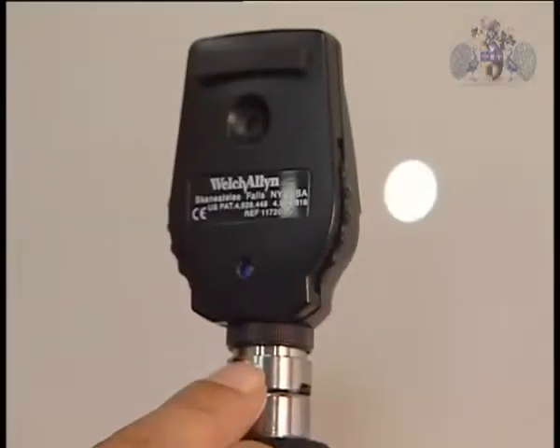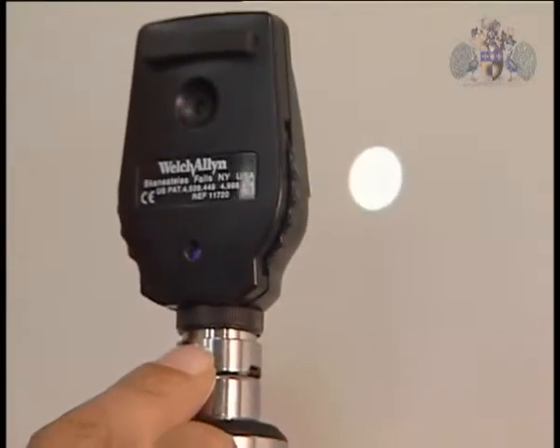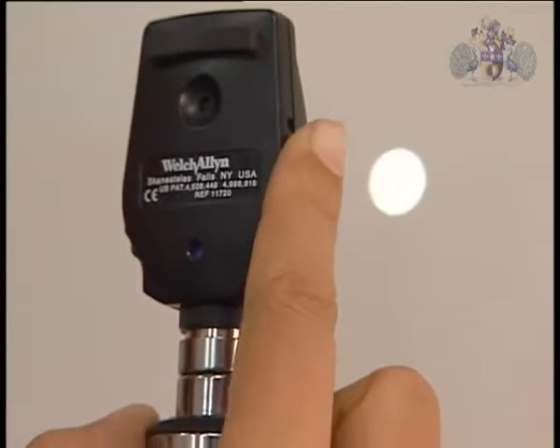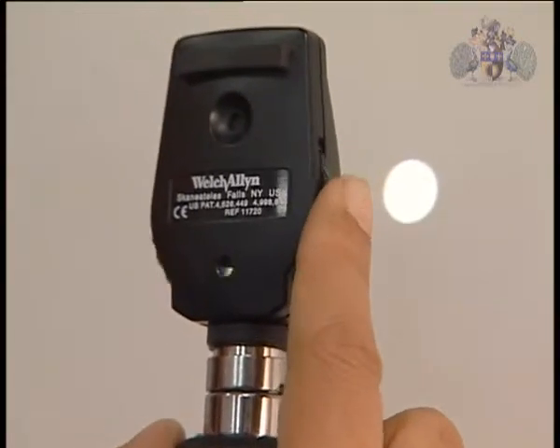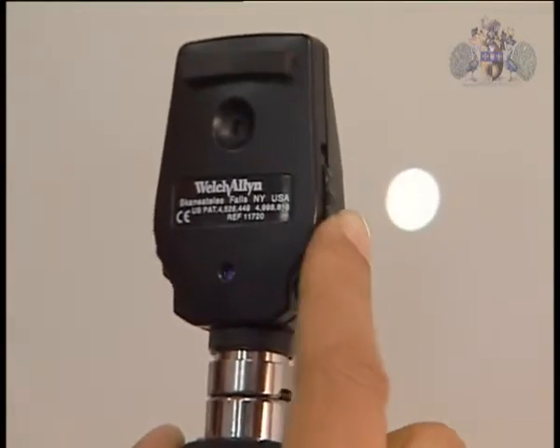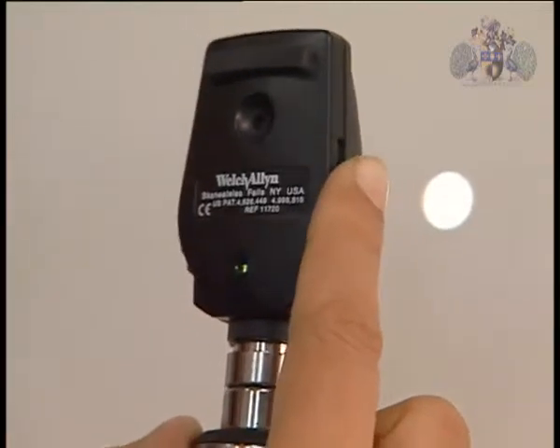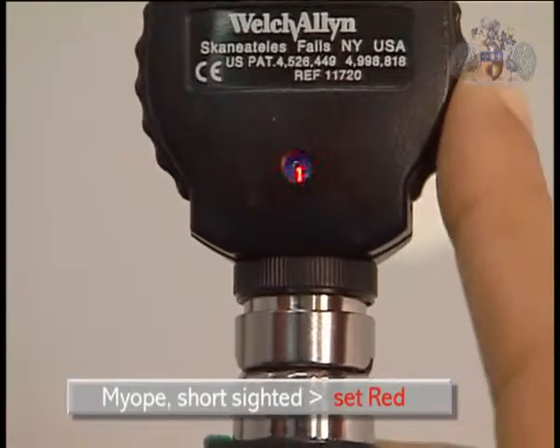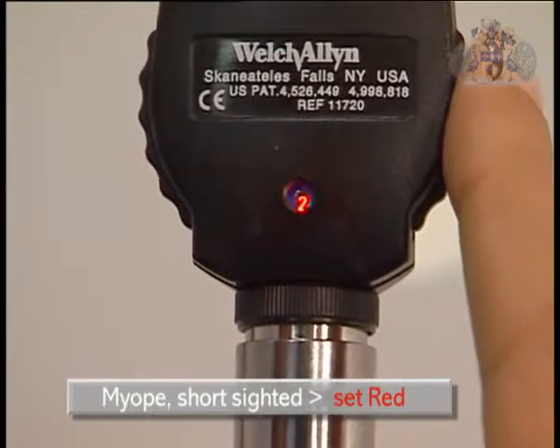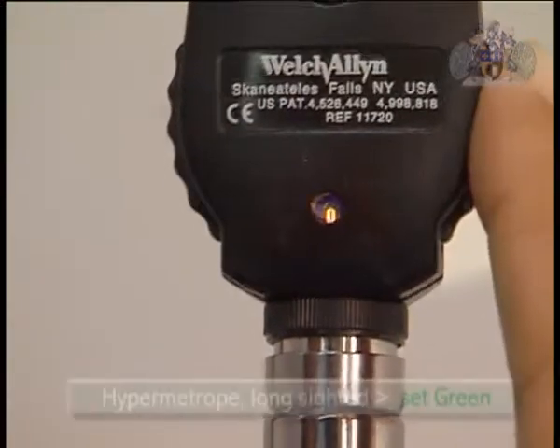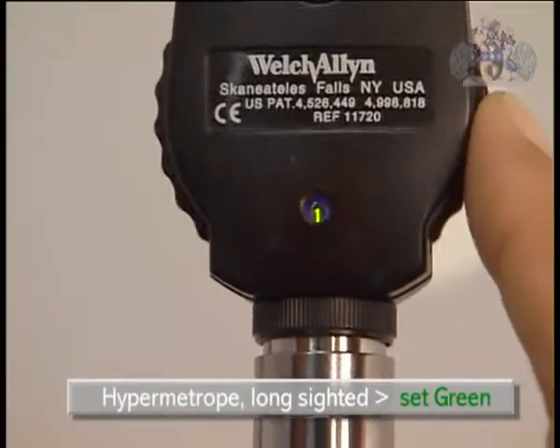If you have a refractive error and you know what it is, you will need to adjust the lens power in the ophthalmoscope to correct for your refraction. If you're a myope, you will set it to a red number. If you're a hypermetrope, you will set it to a green number.